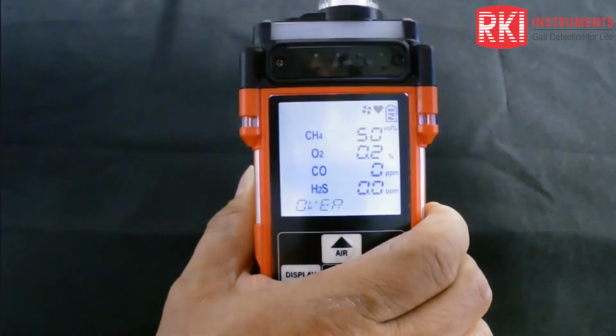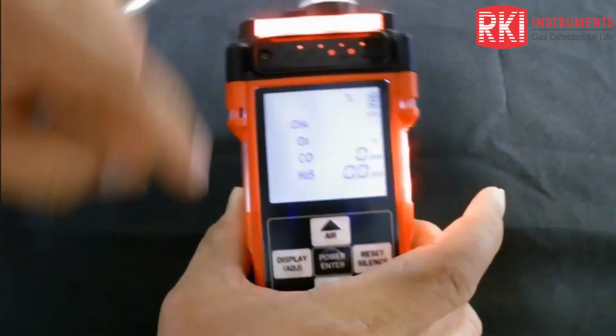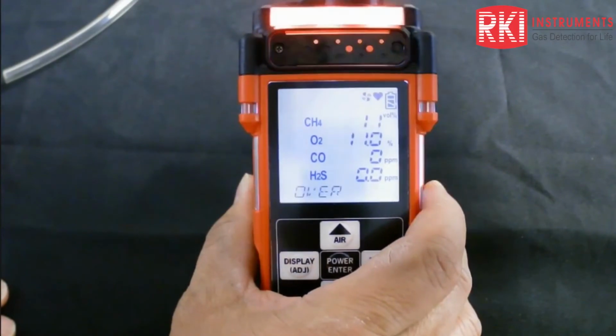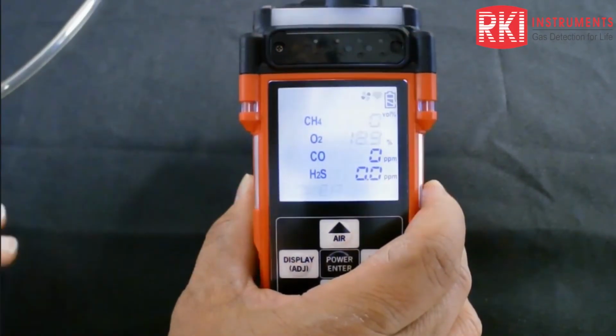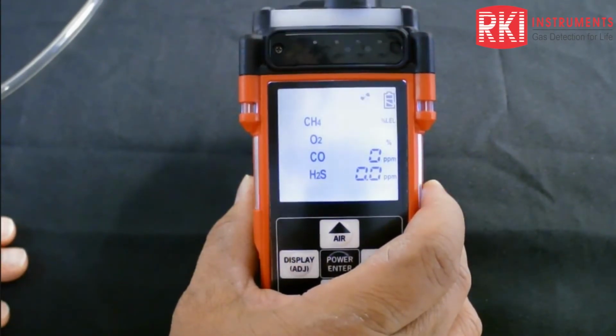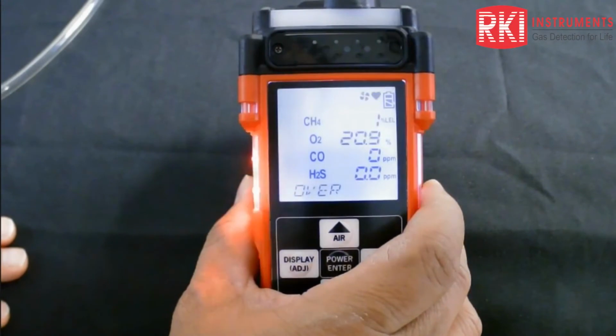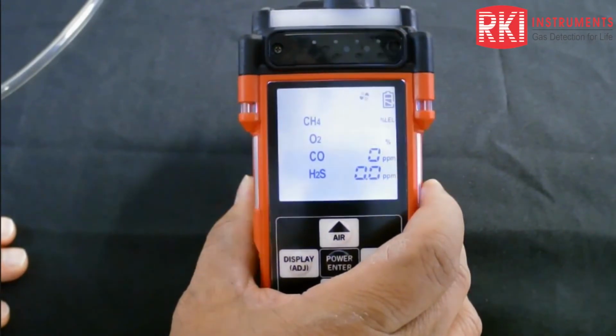If you could silence the alarm, John, that'd be great. There we go. And you'll see, guys, that it went from LEL up to 50. Yeah. So now it's dropping, 20.7. So oxygen is almost to 20.9. So you can see that we're down to 1% LEL.